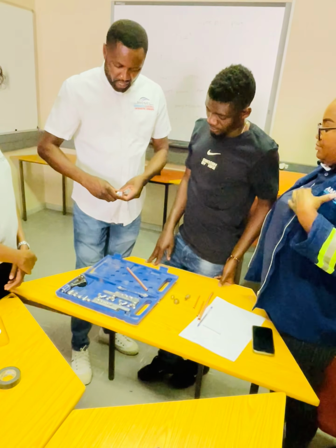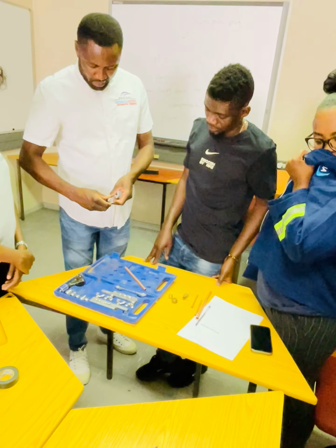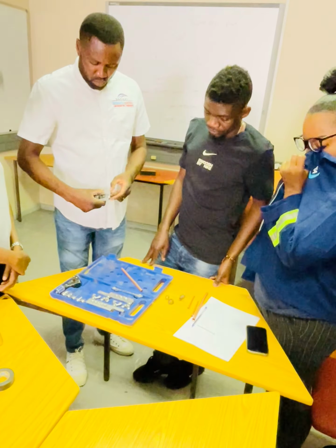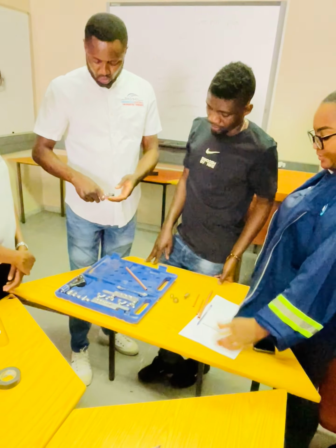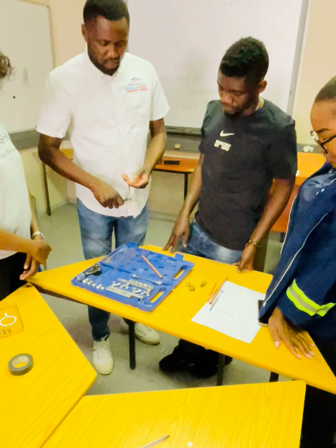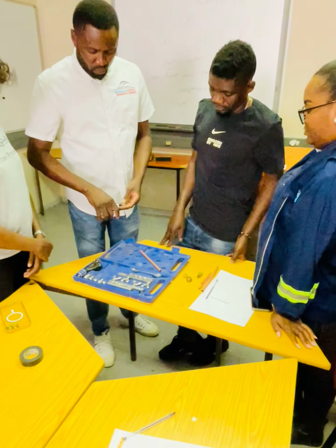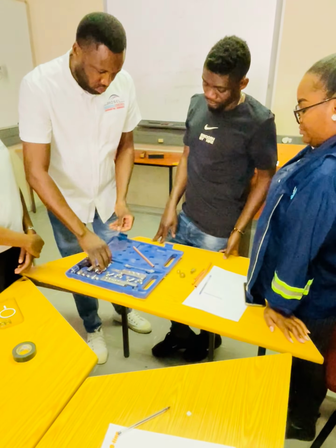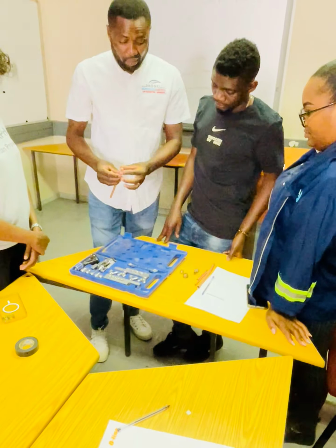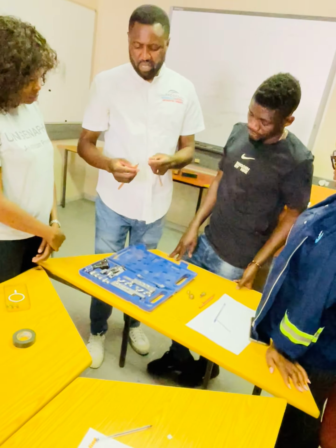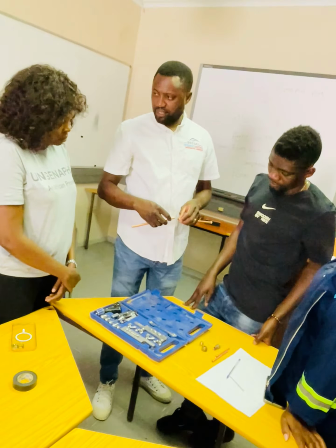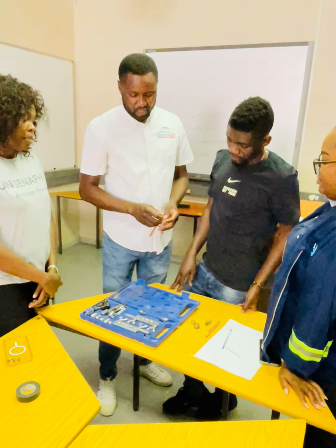Swaging means that we are expanding a pipe to be able to fit another pipe into it. Then we braze it or we weld it. So the pipes must be the same size. One you have to expand so that you can fit the other one in, so that we are able to join them.